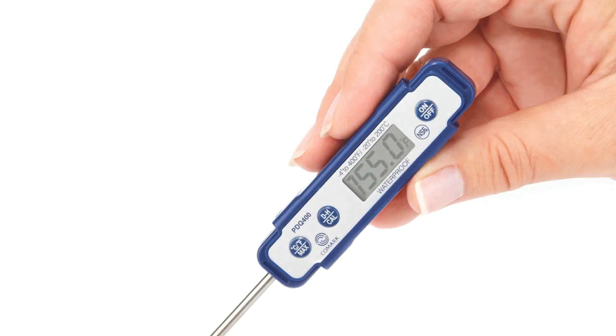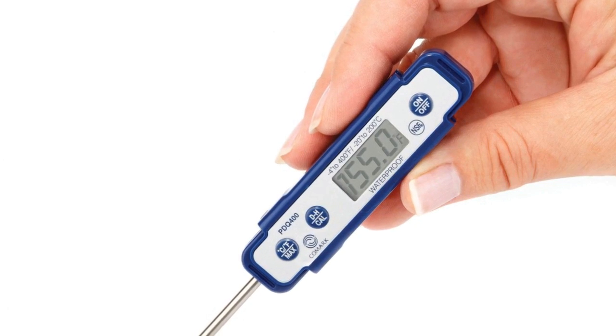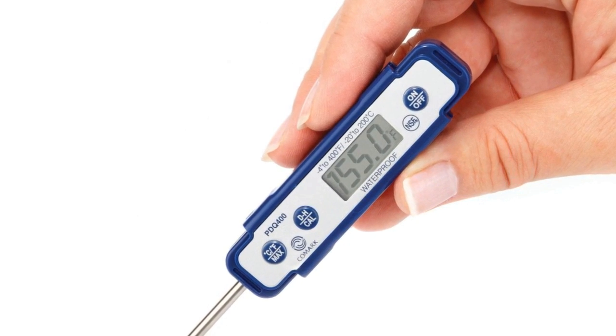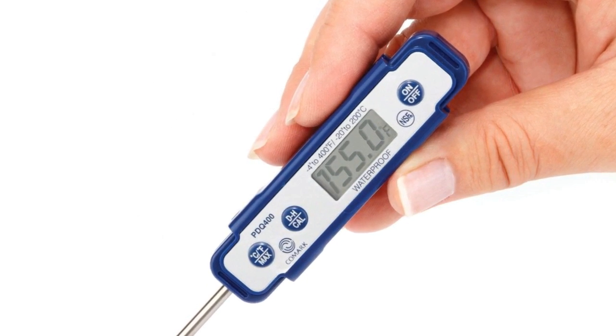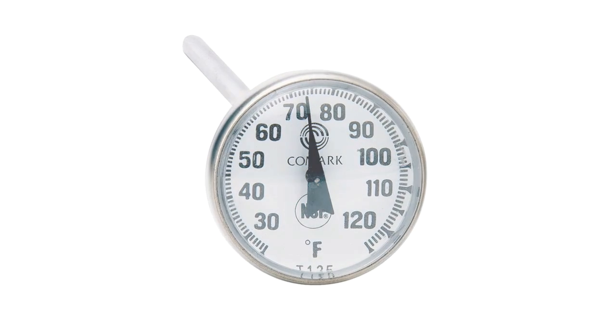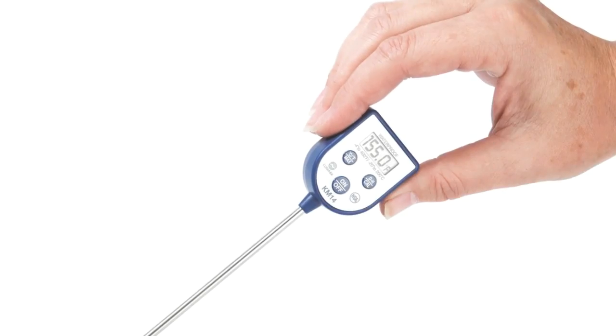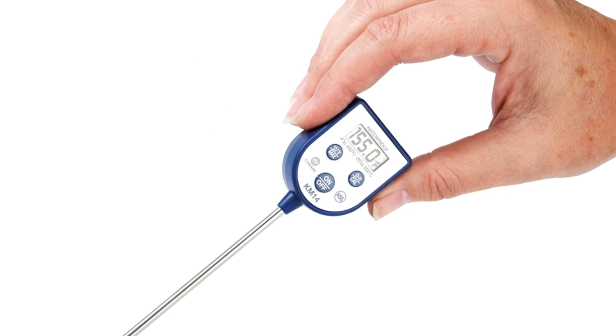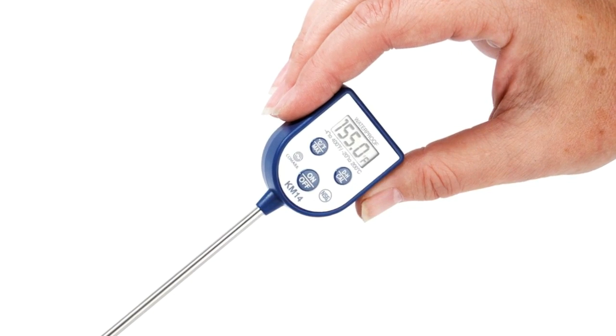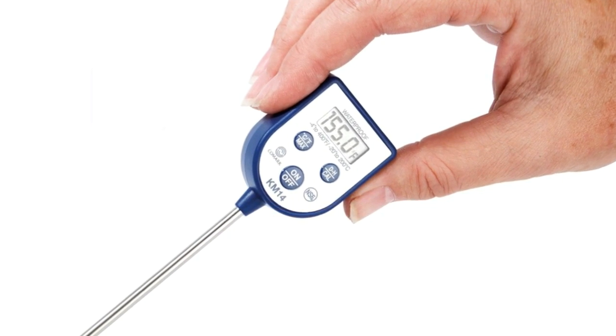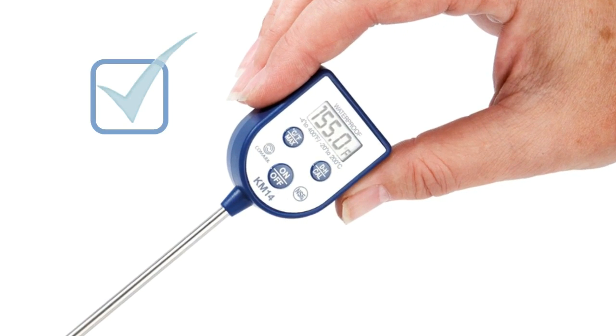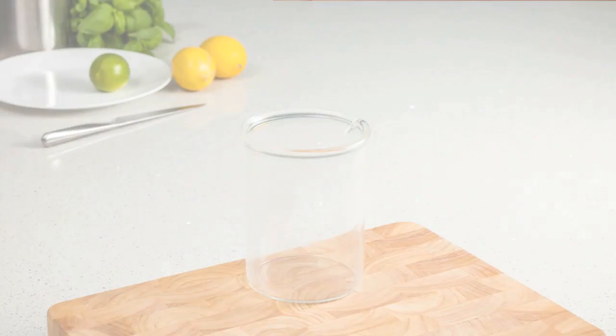As a general rule, temperature measurement devices should be regularly calibrated in order to prove their accuracy. COMARK has a number of pocket digital and pocket dial thermometers that can be calibrated to ensure accurate temperature readings. The goal of the calibration is to verify that the displayed reading you're getting is an accurate one.